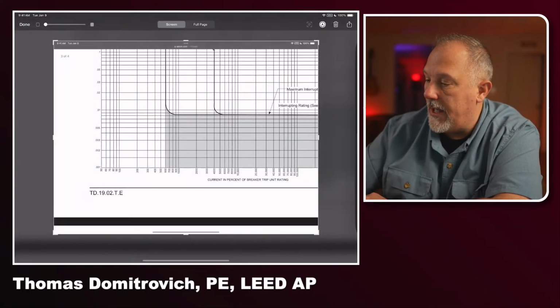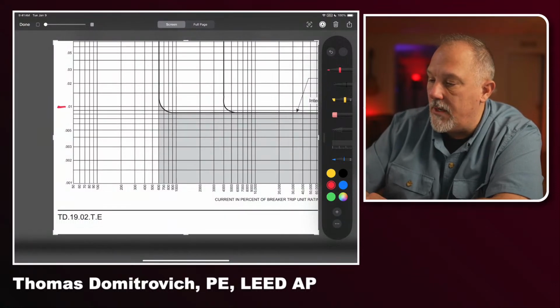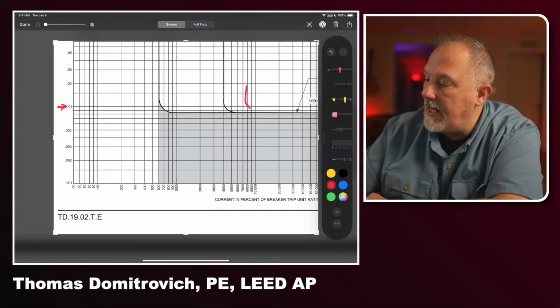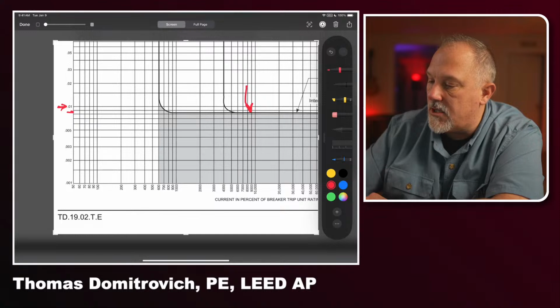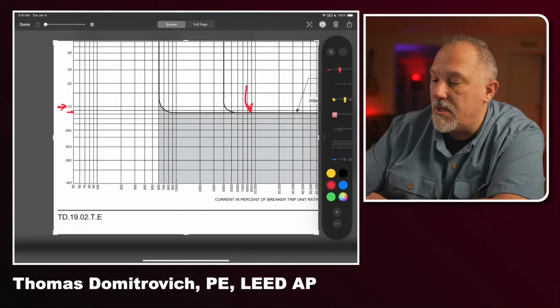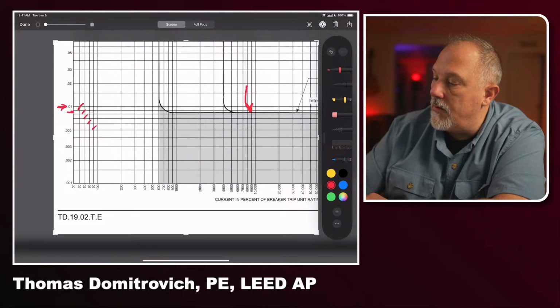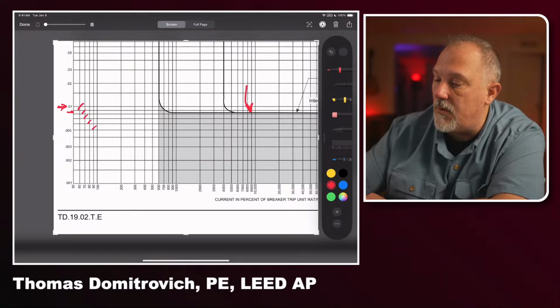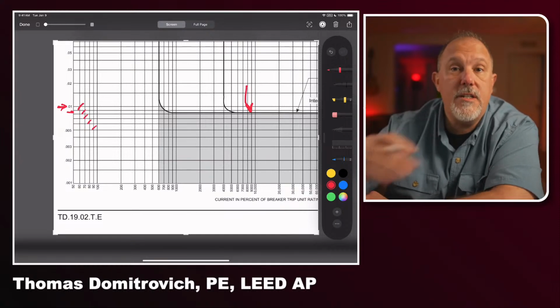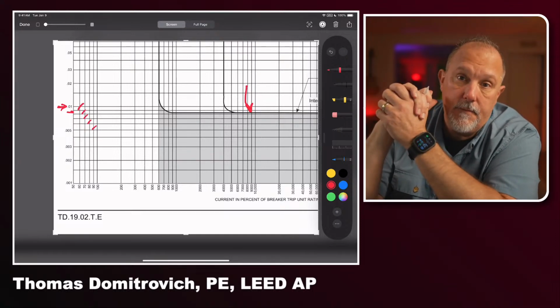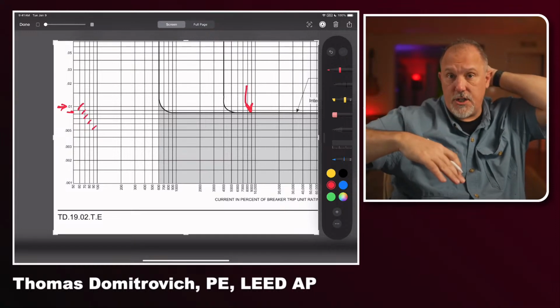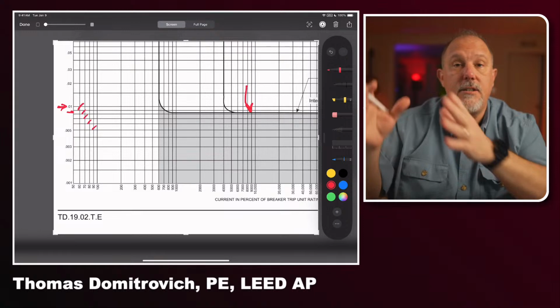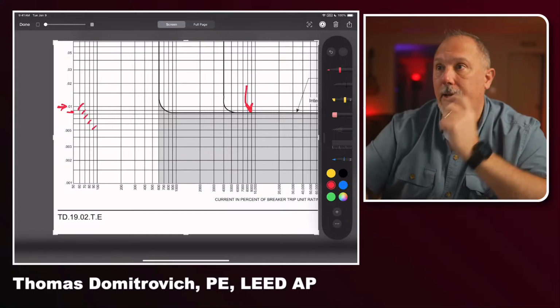So you have, let's make this a little bigger. You have your 0.01 second line right here. The instantaneous is about right there. So if that's 0.01, this is 0.009. There's 0.009. This is 0.008, 007, 006, and 005. So my instantaneous clearing time for this BAB breaker is somewhere between 0.008 and 0.009 seconds, which is faster than 0.01 seconds, and why you don't see it on the screen. And now if I went into SKM and changed my TCC curve, I could show that information, but we never do.